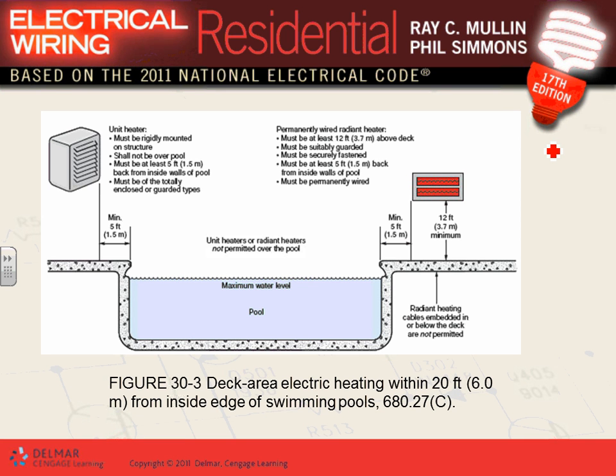Here's an example of how they remove objects like heaters, for example. The code requires, I have a radiant heater in this area, and I have a unit heater in the other area. So they require you, look at that, minimum. Do not get them closer than 5 feet. That's code, from the edge of the water.